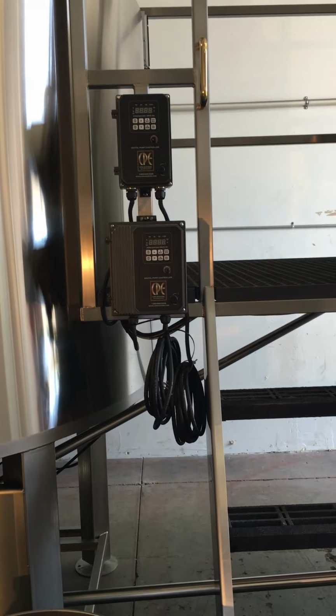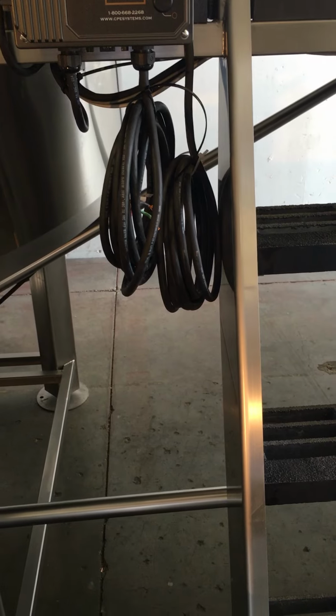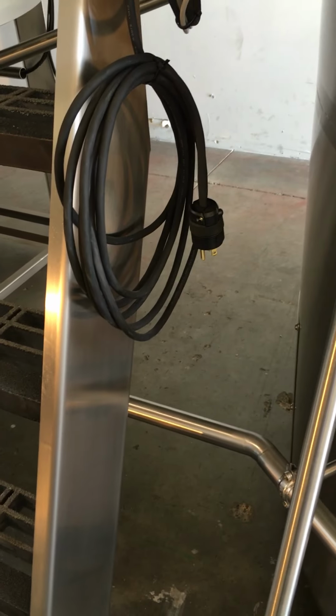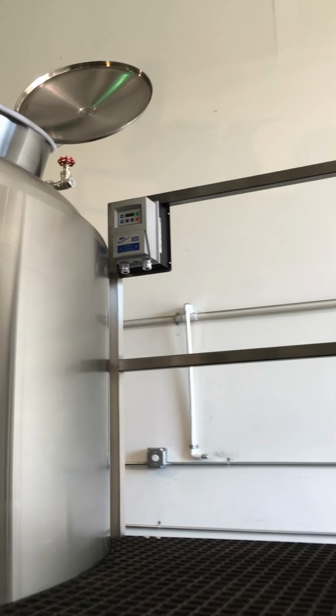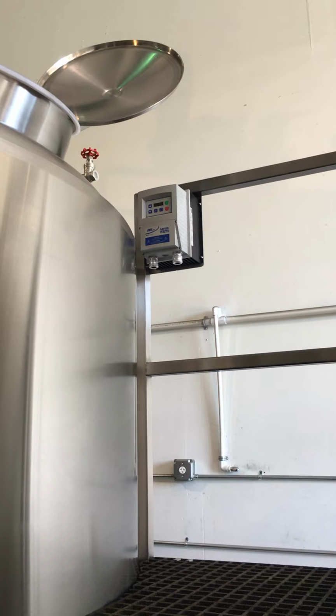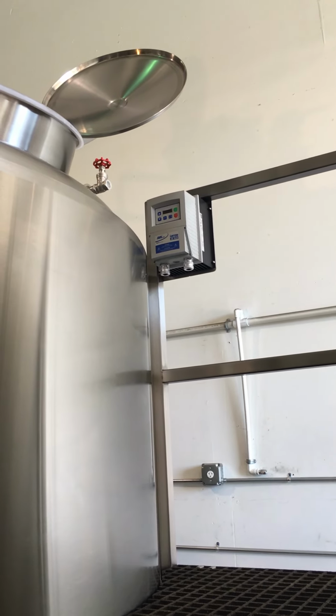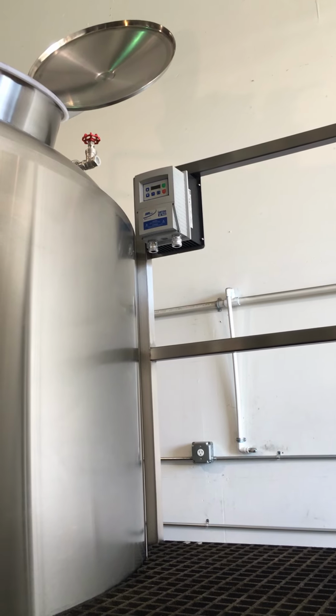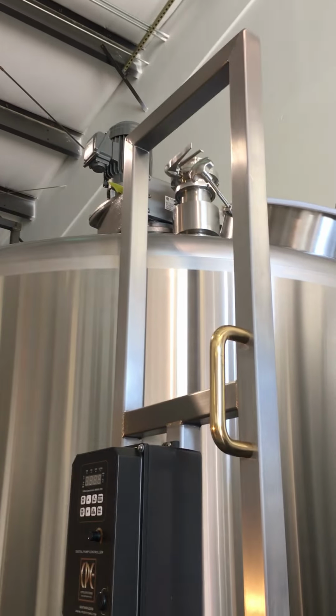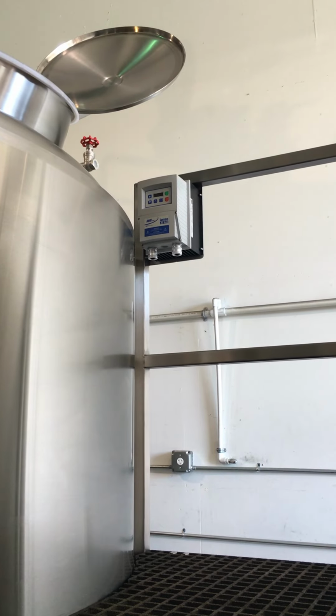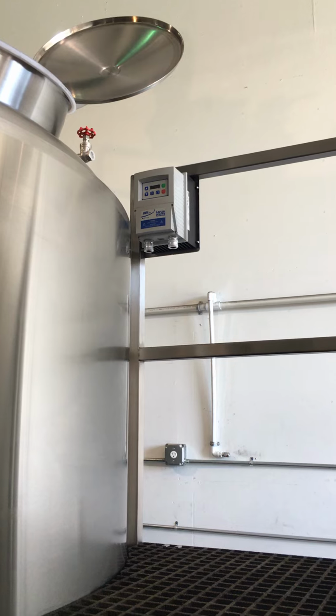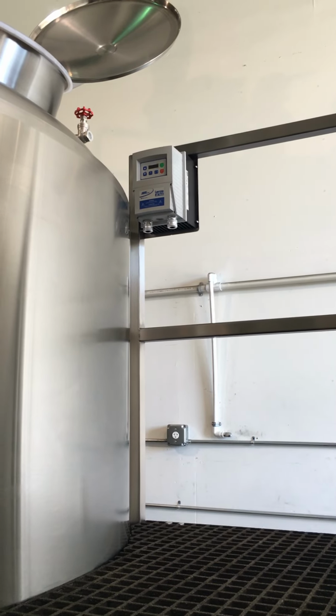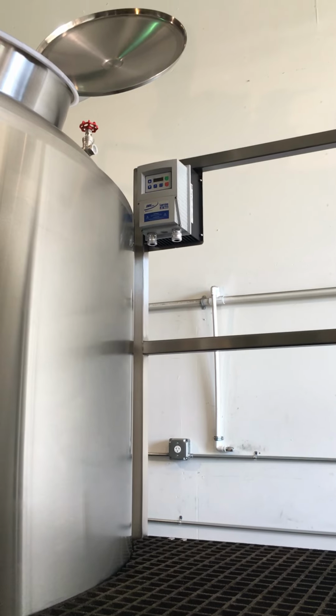And basically all you have to do is just hook up some plugs and plug it in the wall. And the same goes for the brew house control panel. It's already got a plug on it. That's just 110 power. The VFD up here is for the mixer. Now that one is going to have to be wired in by an electrician. You will have power to the VFD, and then from the VFD a cord going over to the mixer motor. There's a program in there to change it to multi-direction that will have to be done. It's simple. It's P112, and you can see that in the manual that comes with it.